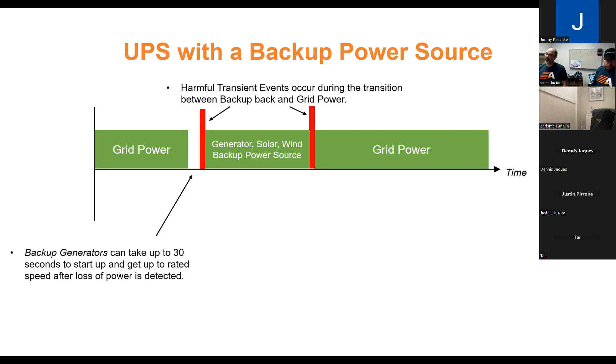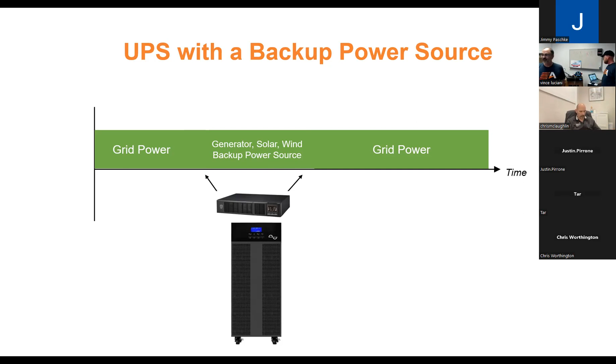When you use a double conversion online UPS, a voltage regulating UPS, all of that is smoothed over. There is no transfer time. I don't think we emphasized that before, but there are no relays for normal operation. There is a relay inside these units if you want to purposely bypass the unit, but during normal operation, when the AC goes away, the batteries just take over that DC bus seamlessly. There's no transfer time at all, and that's the beauty of this system.